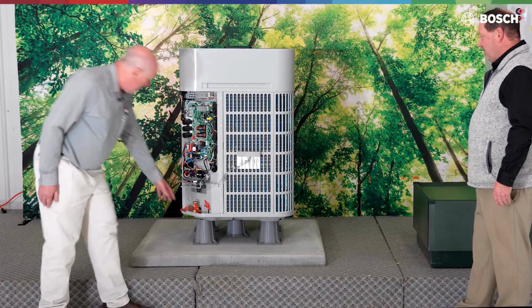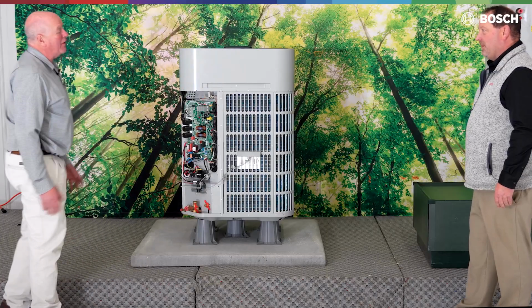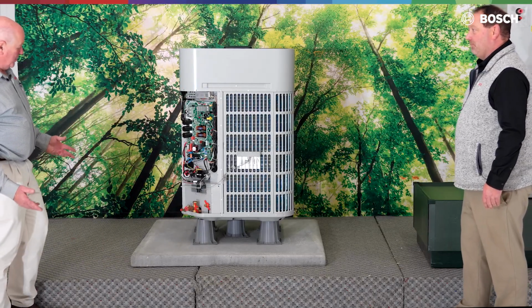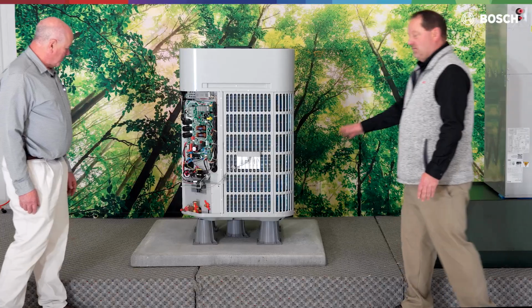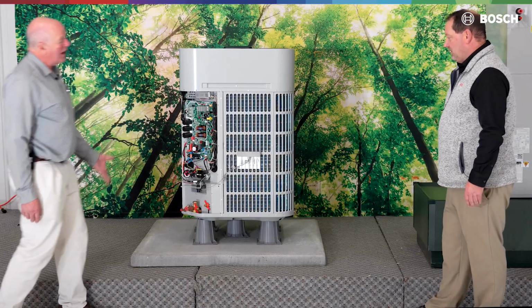Our goal is to keep this 8 inches off the ground so we have no issues with water freezing on that coil and giving us issues. So plenty of room for defrost water. Absolutely. Oh, so perfect. Chris, let's talk about our line set. We've got to hook that bad boy up.